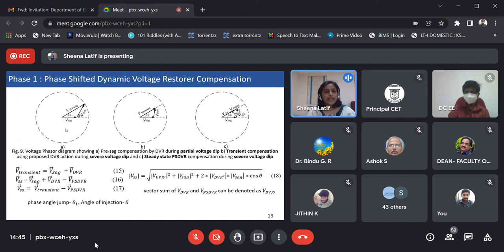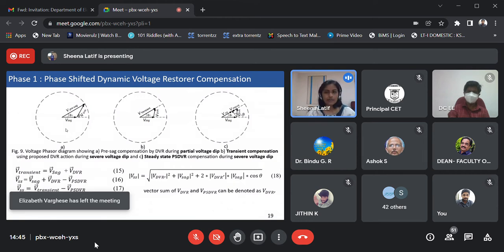Figure A shows the partial voltage dip compensation usually done by the DVR mode, where theta 1 is the phase angle jump. The sag voltage is lesser in magnitude compared to the pre-sag voltage, which is compensated in both magnitude as well as phase angle by an angle of injection theta by the VDVR. Now coming to the PS-DVR mode that we have proposed, figure B shows the transient mode and figure C shows the steady state mode of action of our PS-DVR.